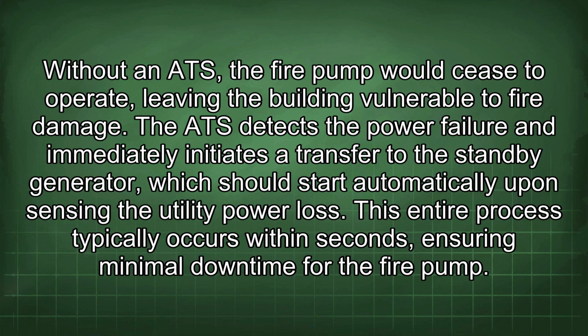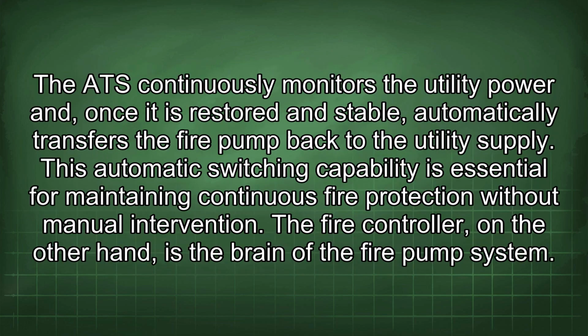The ATS detects the power failure and immediately initiates a transfer to the standby generator, which should start automatically upon sensing the utility power loss. This entire process typically occurs within seconds, ensuring minimal downtime for the fire pump. The ATS continuously monitors the utility power and, once it is restored and stable, automatically transfers the fire pump back to the utility supply. This automatic switching capability is essential for maintaining continuous fire protection without manual intervention.